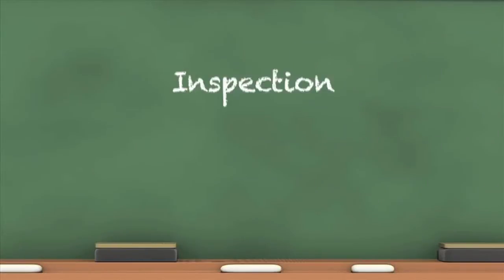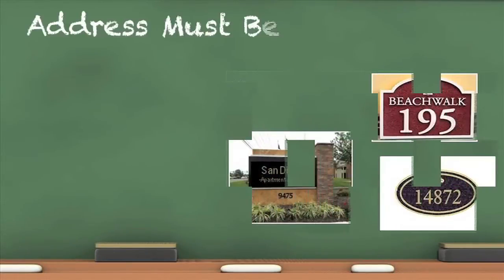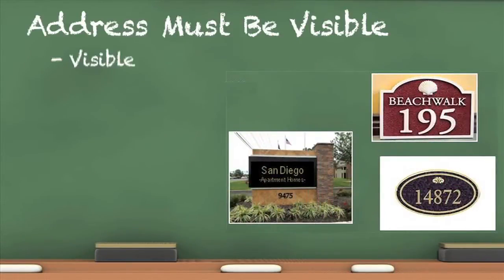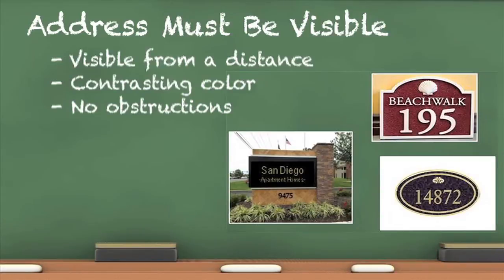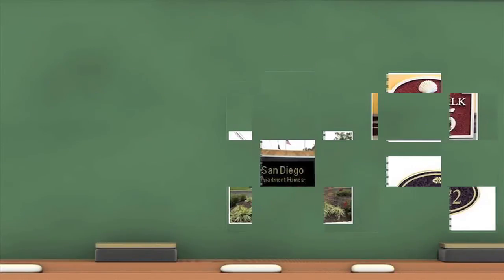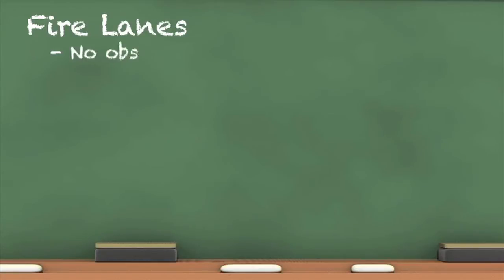Let's start the inspection. It is critical the address is visible. If we can't see the address, fire department arrival will be delayed. Fire lanes need to be kept clear at all times, and the markings need to be easily identified.